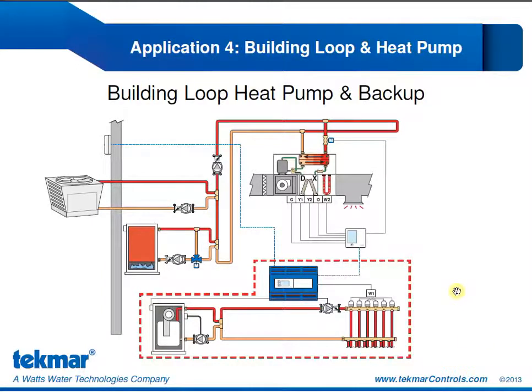Our second heat pump application, the fourth application overall, is the building loop, heat pump, and backup. Again, we have the option of including a radiant floor, noted as optional with the dashed red line. If we include the radiant in the system, that is our first stage of heat. Notice this time the 557 is not going to a house control for that radiant operation, it's going to a TN4 control. And that's because this type of application is really seen only in commercial situations where we wouldn't likely use a house control. We're more likely to use the designer series.